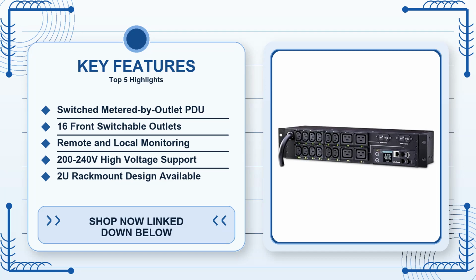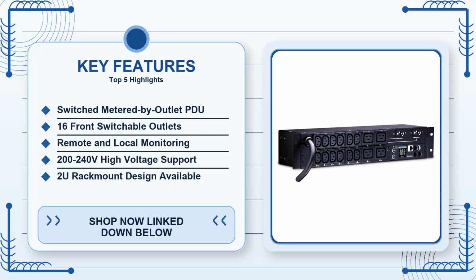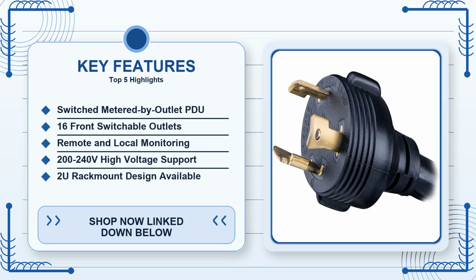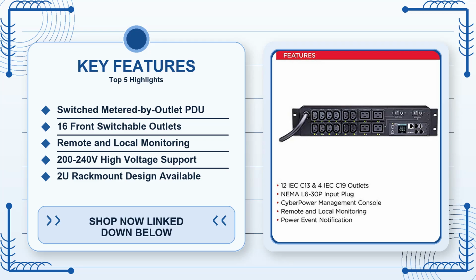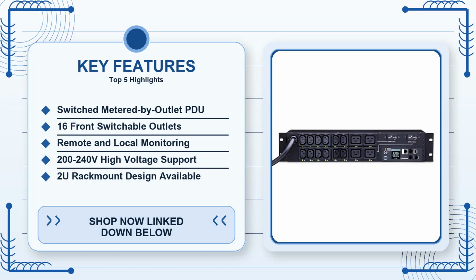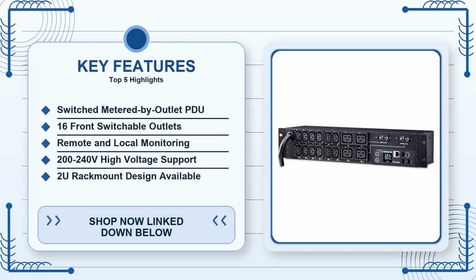The PDU is 200-240V and rated for 30A, but it's derated to 24A to stay within the safe operating range for most small to medium installations. That means if you accidentally load the unit beyond 24A, the internal protection will trip, potentially shutting down all 16 outlets, something you might not notice until you get a notification from the monitoring software. For a hobbyist who isn't using a UPS or a dedicated circuit, the risk of overload is real, and a simpler strip would suffice.